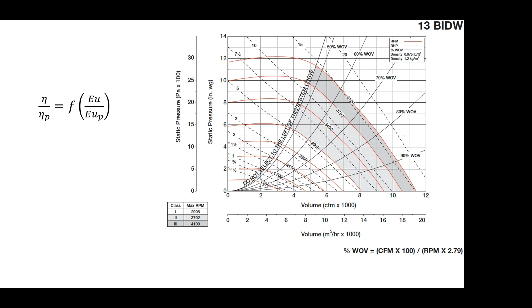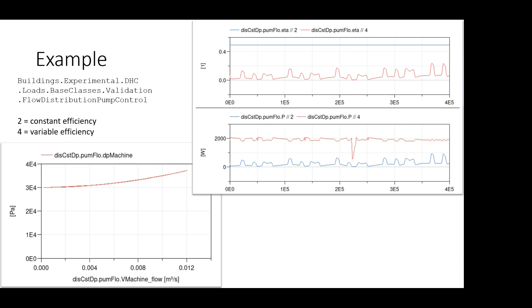We have one more example here. We tested it on many large models. This is a quick comparison of the model with regard to the efficiency of the fan and the pump, and the power consumption of the pump. This pump in this model operated along this line here. If we use the old model, where we assume a constant efficiency of 0.49, so 0.7 of hydraulic efficiency times 0.7 of motor efficiency, then we have a much lower computed power consumption. But if we use the new method, with variable efficiency for both the hydraulic and motor efficiency, we end up with a much larger number for power consumption. So this method certainly has potentially large impact on any large-scale models you might be building.